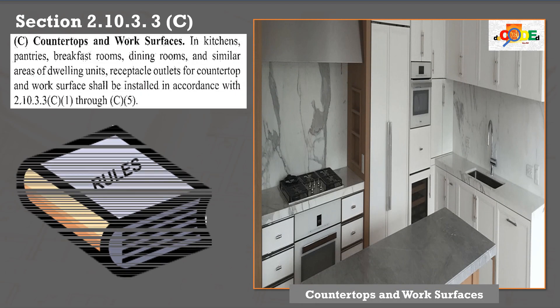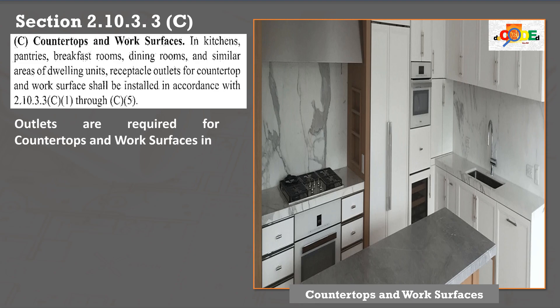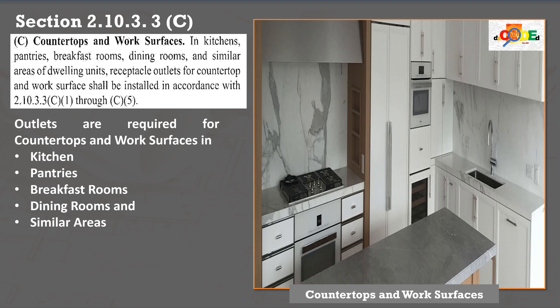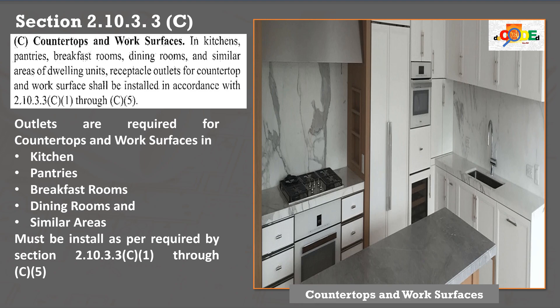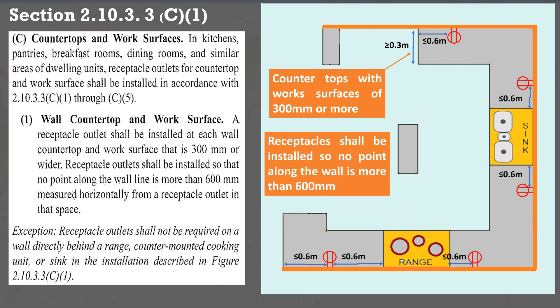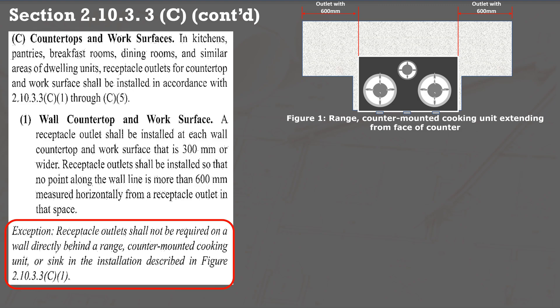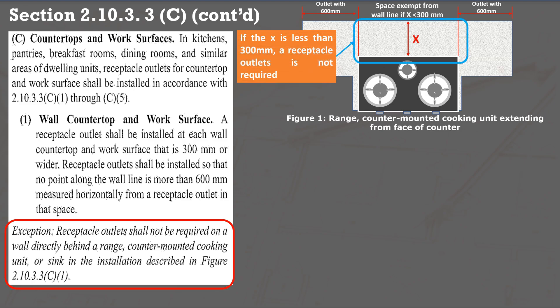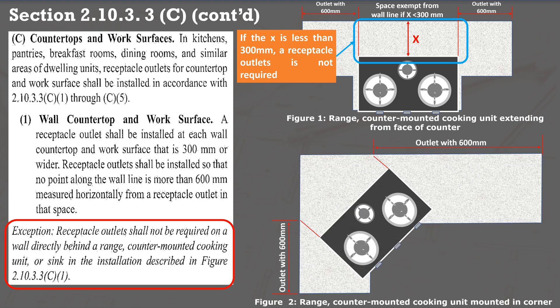For countertops and workspaces, in section 2.10.3.3 C, an outlet is required in countertops and work surfaces of kitchens, pantries, breakfast rooms, dining rooms, and similar rooms, complying with sections C.1 through C.5. Paragraph C.1 states that a countertop 300 mm or wider shall have an outlet such that no point on a wall is over 600 mm or 24 inches from an outlet, with a maximum distance between two outlets of 1,200 mm or 48 inches. Exception: for a cooking range extending from the face of the counter, an outlet is not required if the distance between the back of the range and the wall is less than 300 mm. If the cooking range is mounted in a corner, no outlet is required if that distance is less than 450 mm.